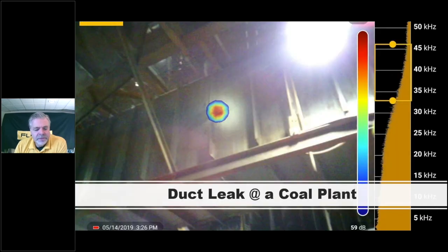So we talked about vacuums. Duct leaks on a coal plant is a great example of what we do with vacuums. The turbulent air that gets pulled through into the vacuum generates the high frequency, and we can find it very quickly.